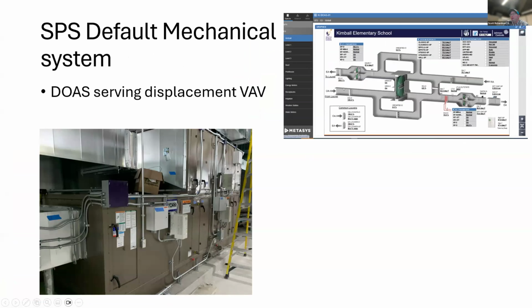As far as air quality here, we use DOAS heat recovery systems. Here is a graphic of that, where we have outside air coming in. The outside air will pick up energy from the return air on the spinning heat wheel. We will provide 100% outside air to these new schools for the increased air quality that they're finding. The more fresh air, the better. If the conditions between outside air and return air aren't right, the heat wheel will turn off and you can bypass around it. Here's our hydronic coil that is served by the water-to-water heat pump plant.